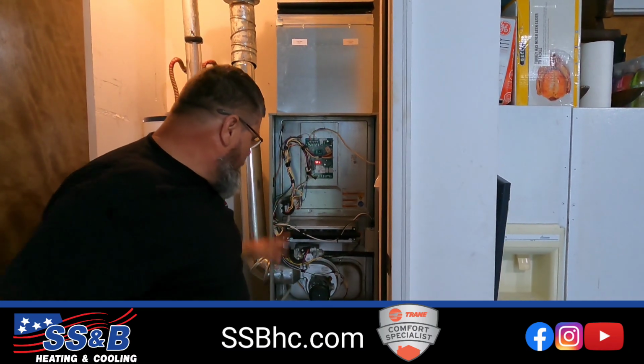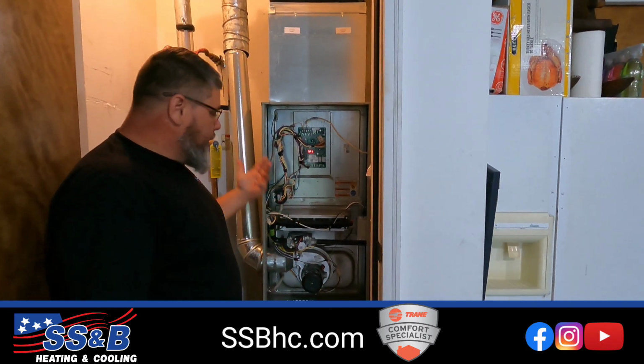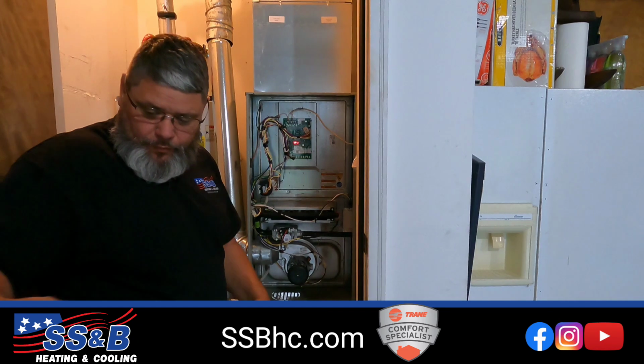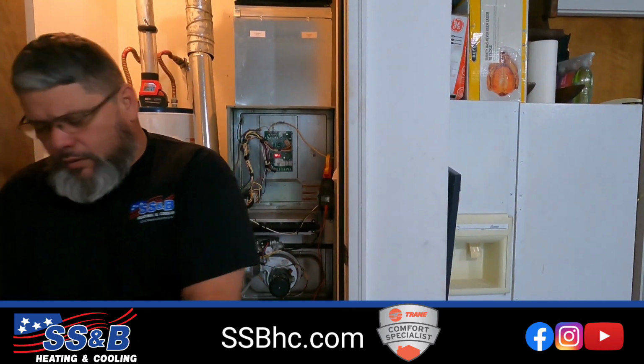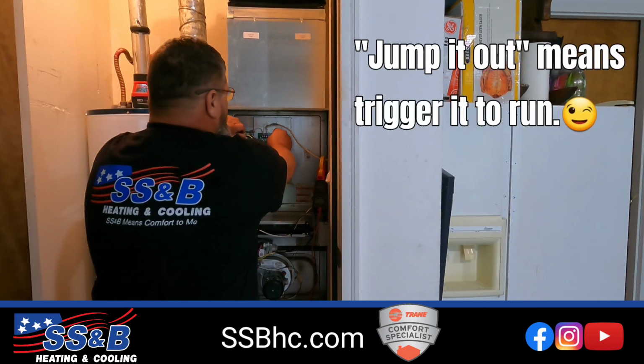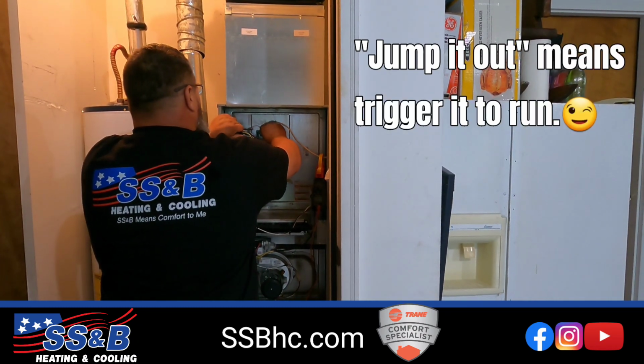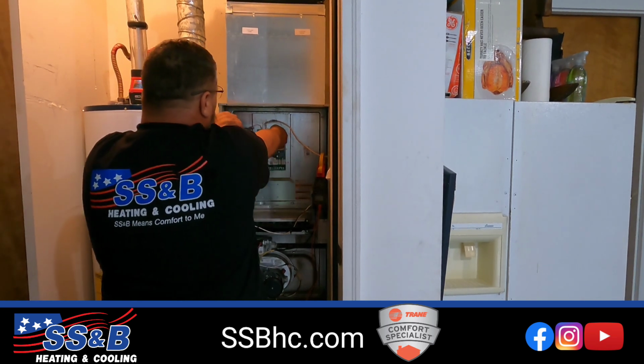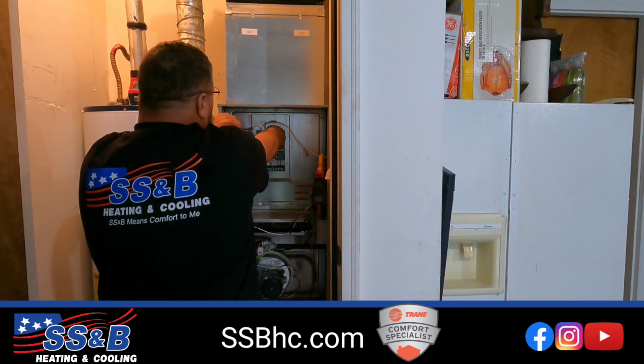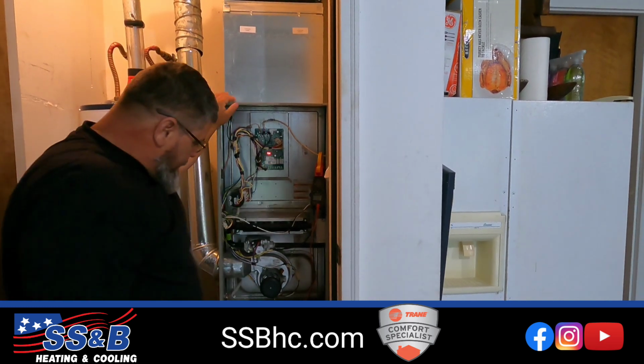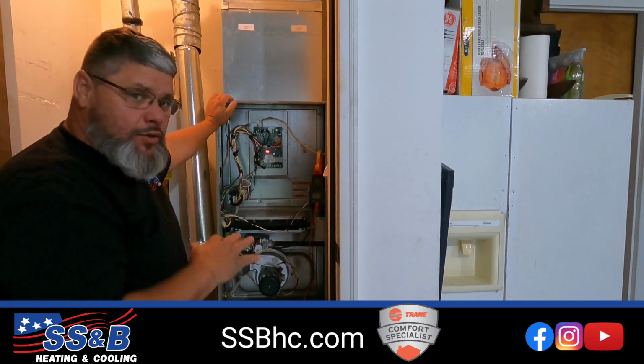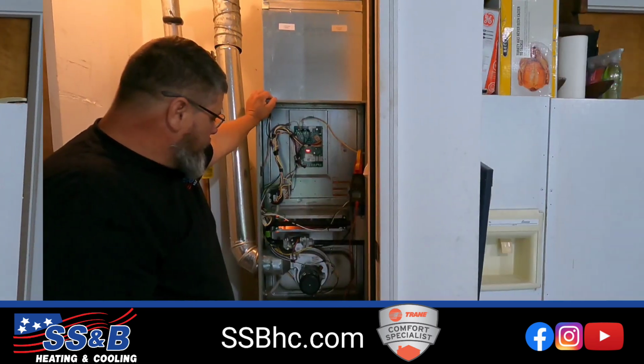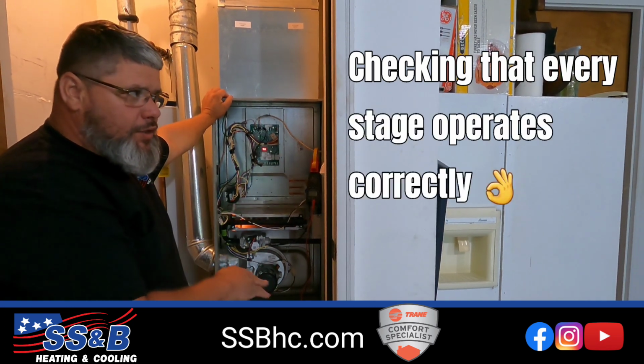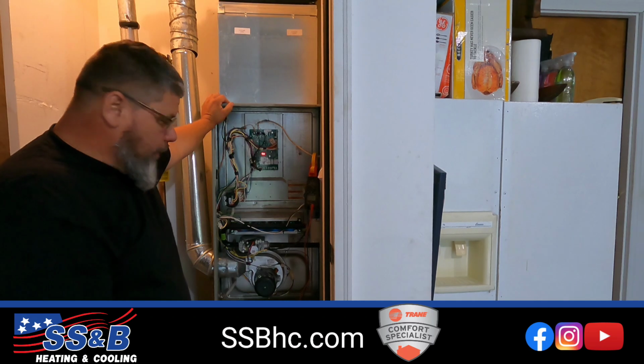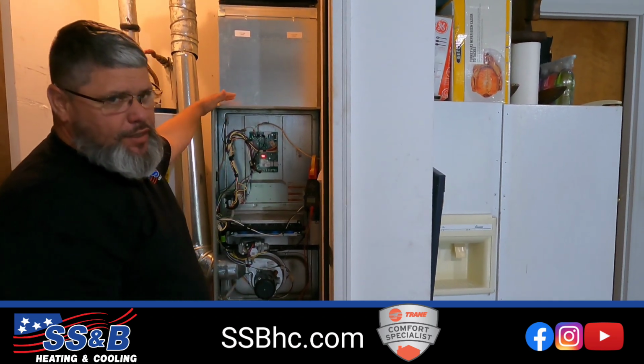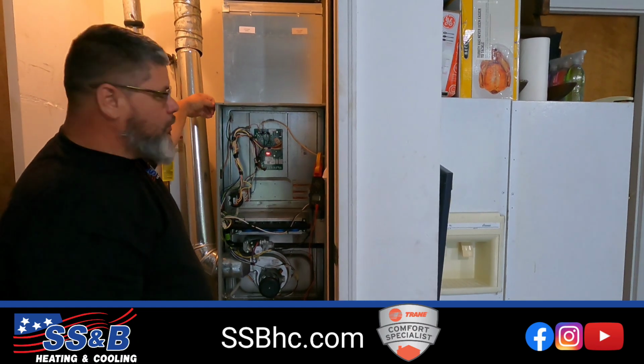This gives us access to all of our electrical and all of our gas valves and everything. From here is where we do all of our testing. We go ahead and we'll jump it out and make sure that the system is operating correctly before we get started. We'll run it through a complete cycle to make sure that everything is working correctly. And this just shows us every stage of this furnace. So we now have a fire, and then after it heats up, then the blower will actually come on, the system will actually run at that point.